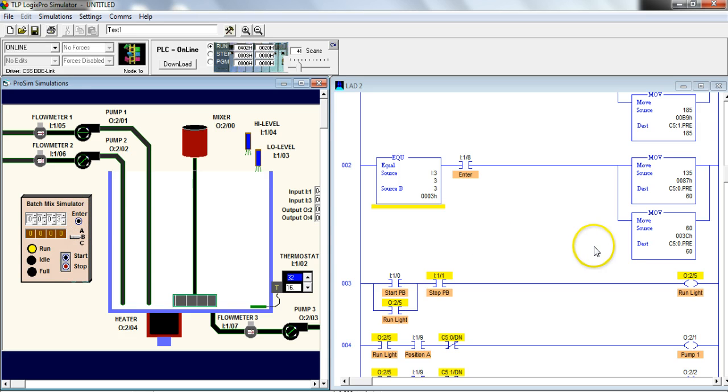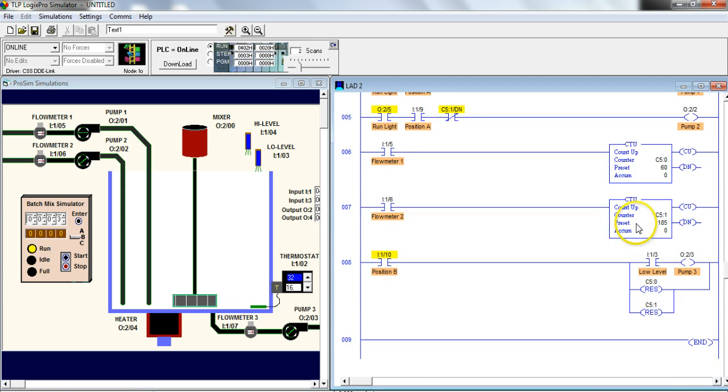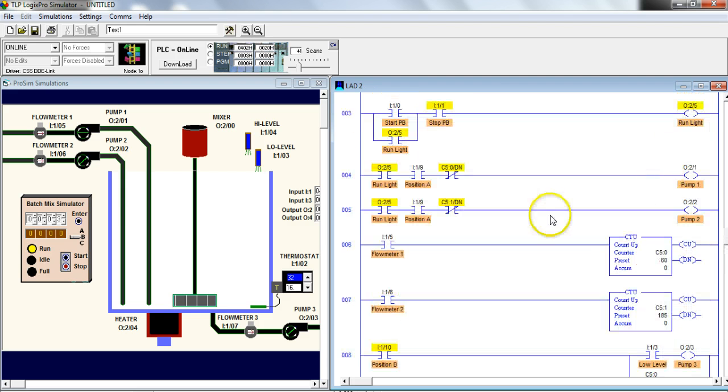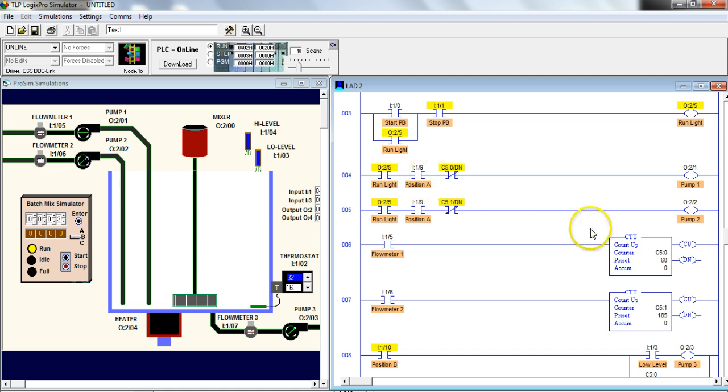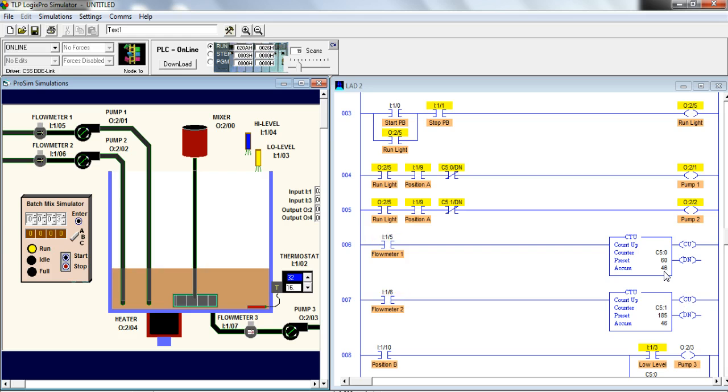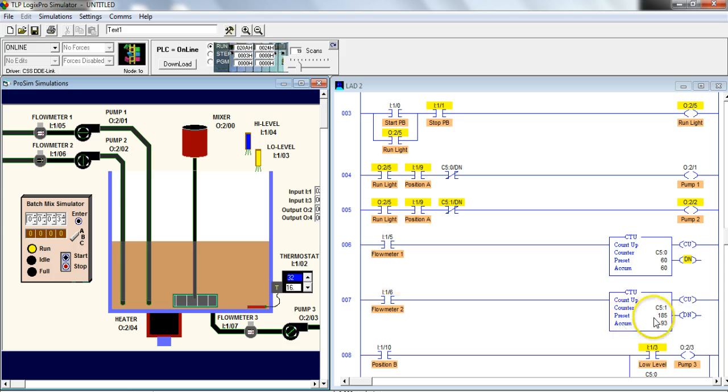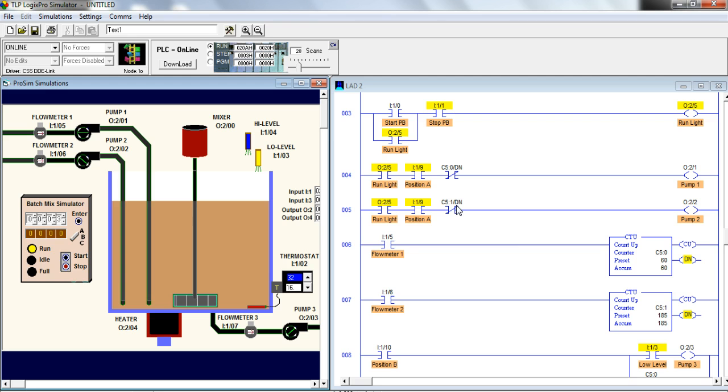And essentially what that's going to do, if I show you this code here, these counters are going to control these pumps. So there's a done bit on the counter. Counter 5-0 has a done bit. And that's right here. If it's not done, then we'll pump up until we get to 60. And then it'll shut off as long as I'm in position A. So if I go to position A, now you'll see it's counting up to 60. It went done, so it shut this one off. This one's counting to 105. This is C5-1. And when this gets to 105, this will go false and shut that pump off.